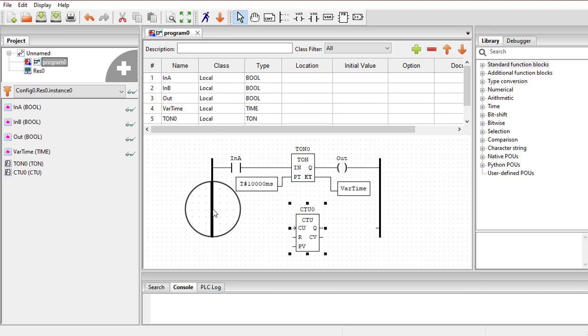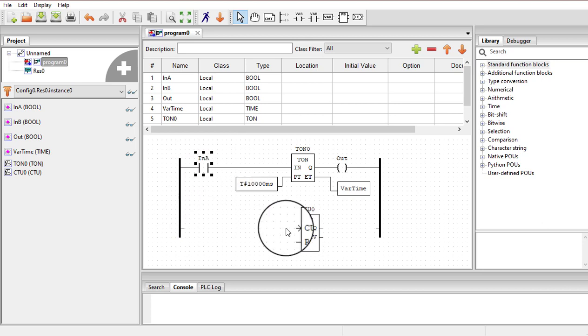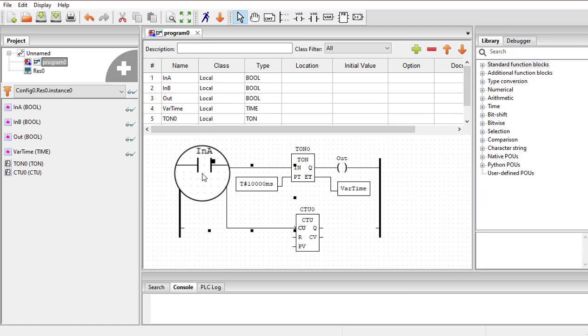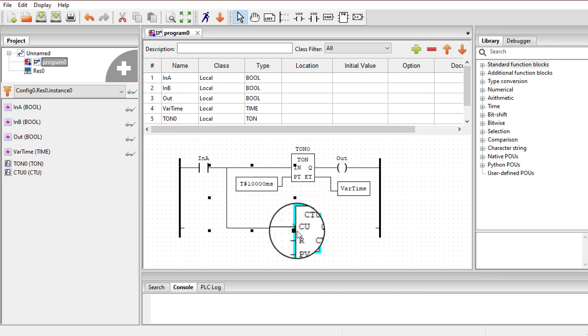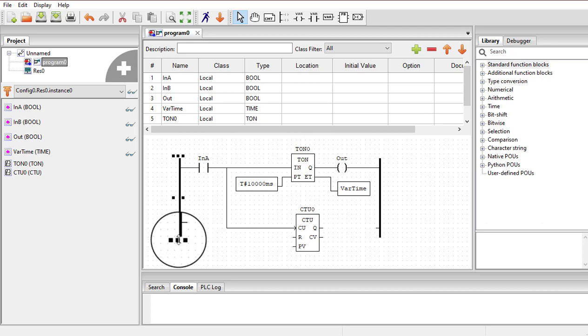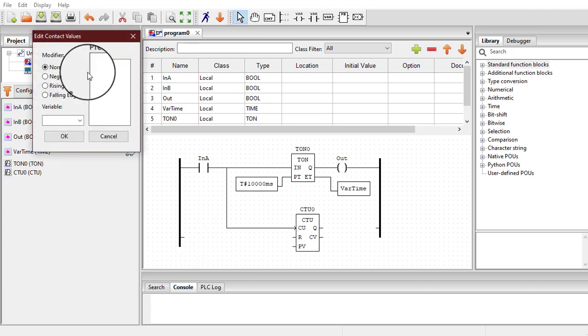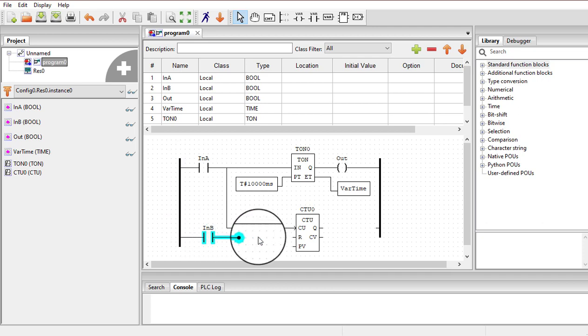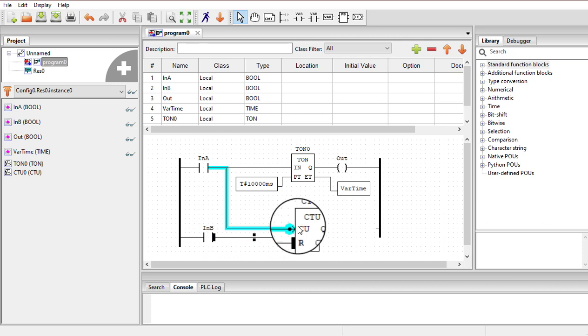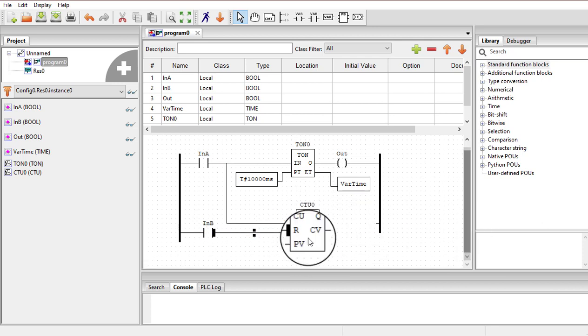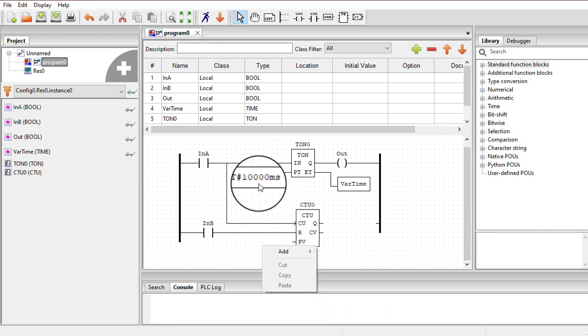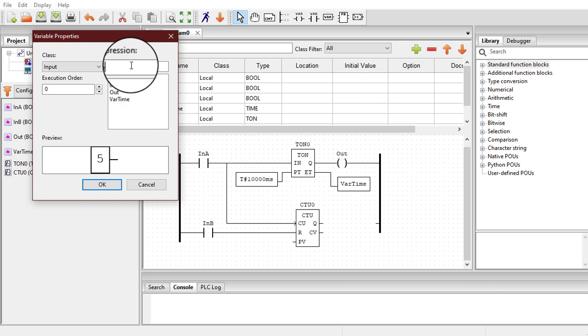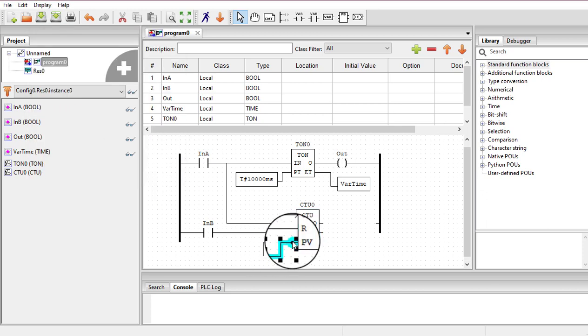In the same ladder diagram I am going to use this counter as well. I can attach the CU pin to input A, so whenever input A turns on the timer starts timing and the counter increments its count by 1. I can also attach input B to the R terminal to reset the counter — whenever input B goes high, the counter will reset. For the preset value, I add a variable and in the expression simply enter 5.